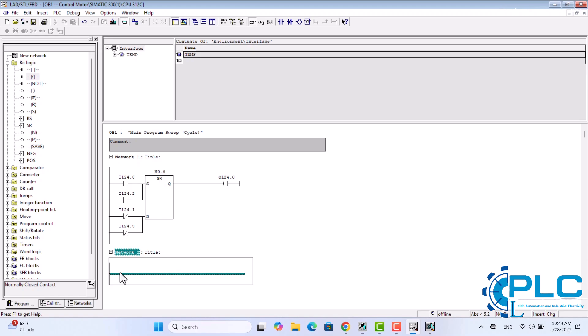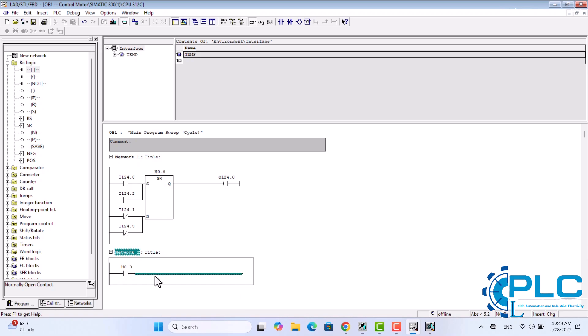In this network, first, I add a normally open contact and assign it the address M0.0. This is the same memory bit used by the flip-flop for the motor. By using this, the light will only flash when the motor is running—no need to duplicate the flip-flop. Next, I insert a second normally open contact with the address M1.5. This is the CPU clock bit we activated earlier from the hardware configuration, and it toggles every one second.